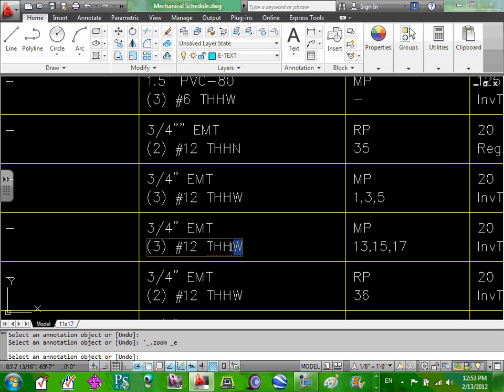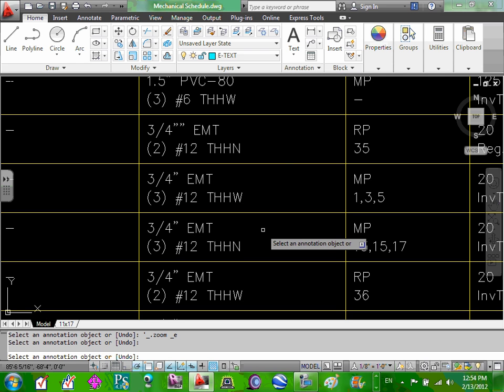So probably you could get away with, unless you're underground or outdoor, it's N. It's not going to change your system. Probably if you look at the EMT, I could have gotten away with a 1/2 inch here, but 3/4 inch is not bad. A lot of people don't carry less than 3/4 inch anyway. Okay.